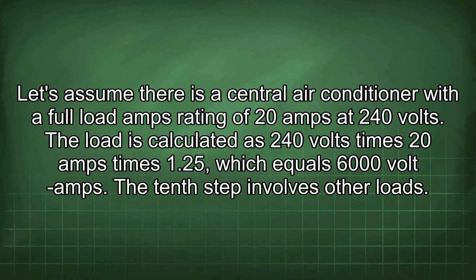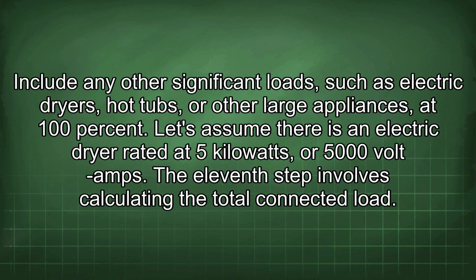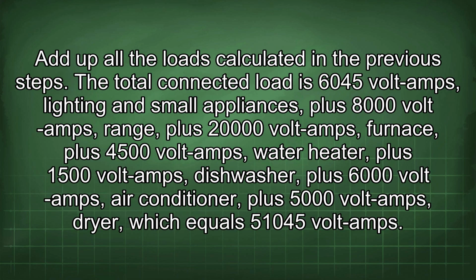The 10th step involves other loads. Include any other significant loads such as electric dryers, hot tubs, or other large appliances at 100%. Let's assume there is an electric dryer rated at 5 kilowatts or 5,000 volt amps. The 11th step involves calculating the total connected load.